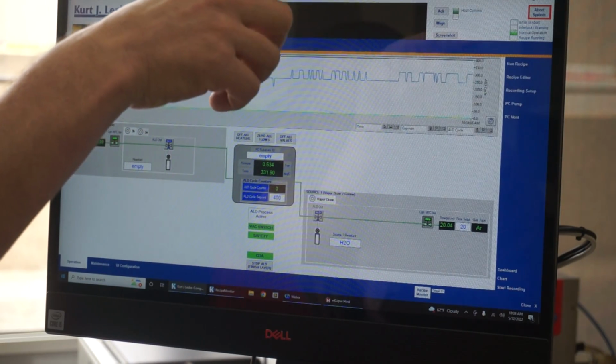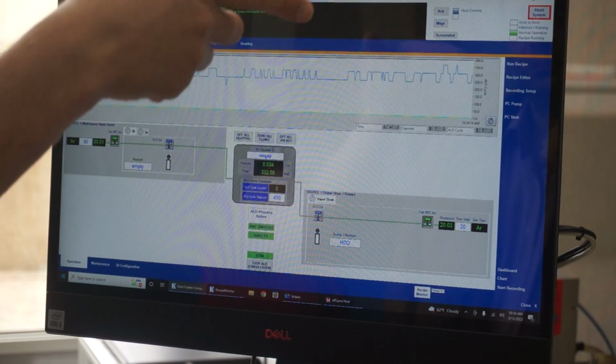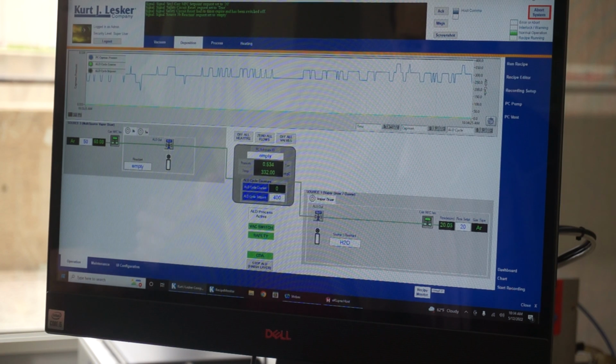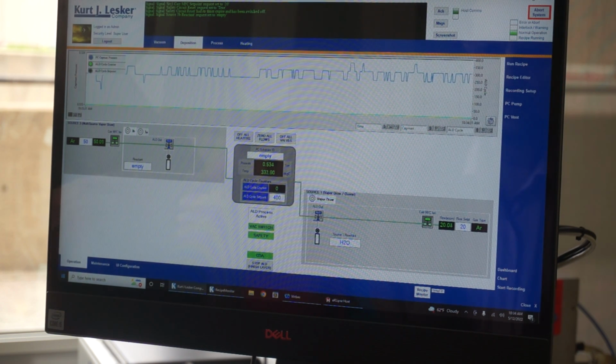Right now you have regular argon or regular nitrogen hooked up to the system. The next time you order an argon bottle, you should order a purity of 4.9s. It's called 4.9. I would have a higher purity level than what you have on there now. For just getting used to the tool and the process, it's fine. But if you really want to get results on a process you're trying to tune down, you should have a higher purity argon than what you have.